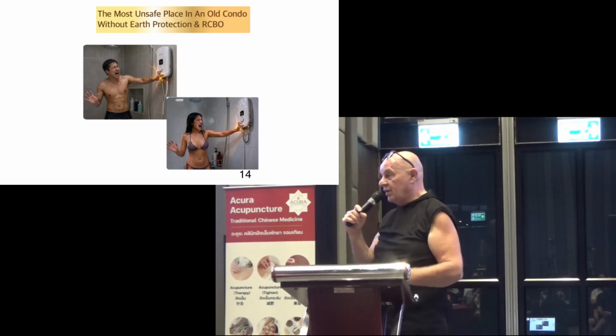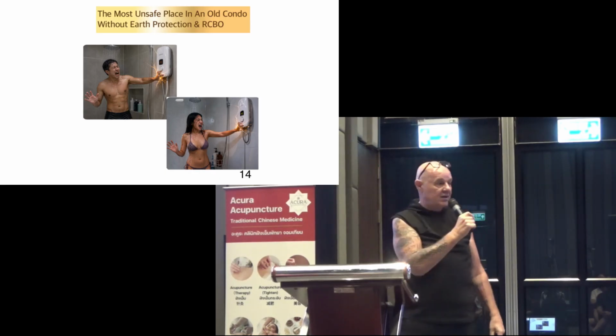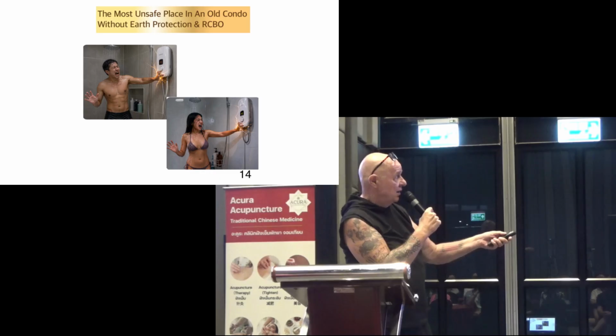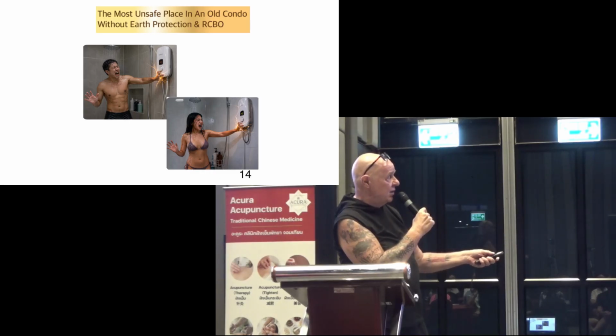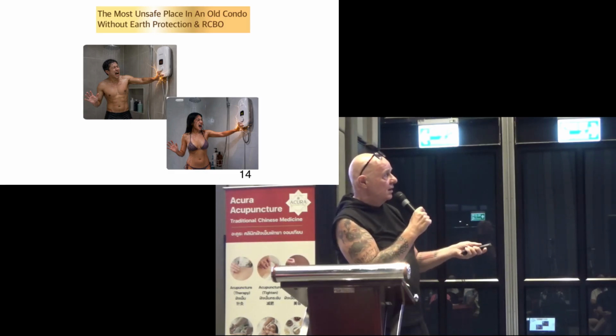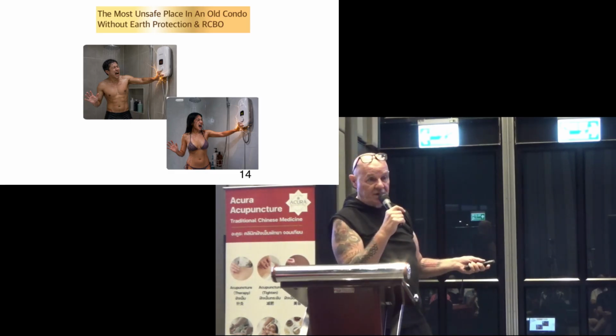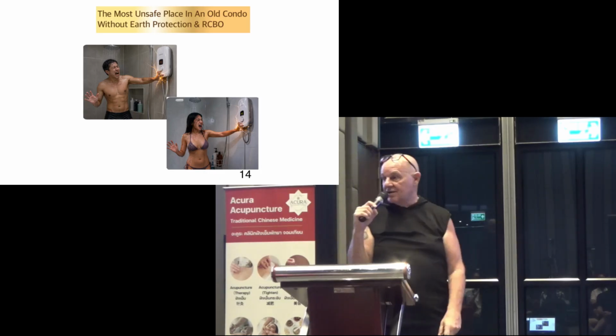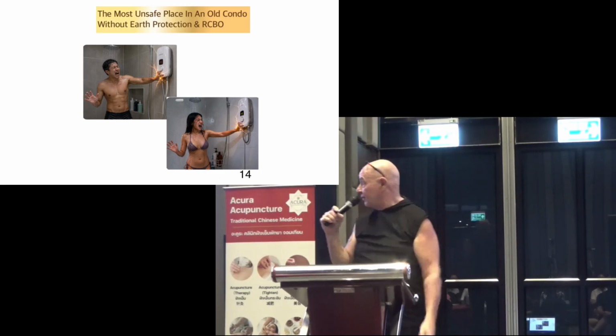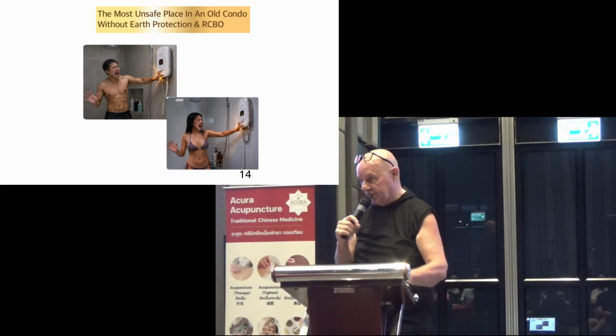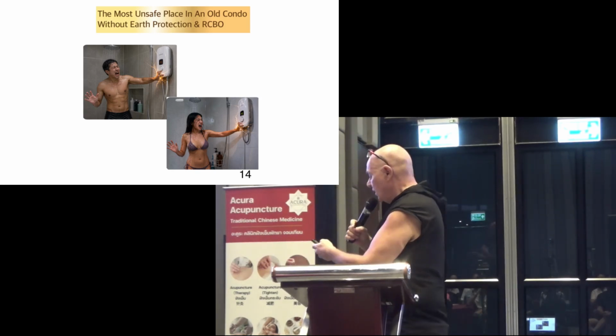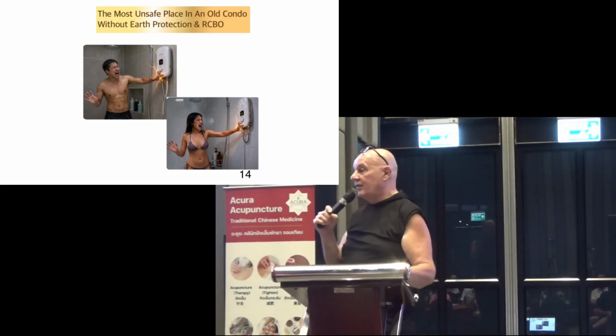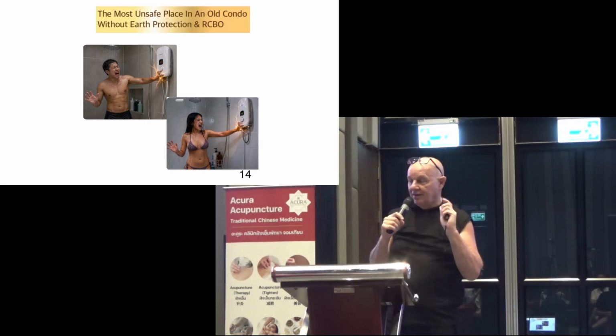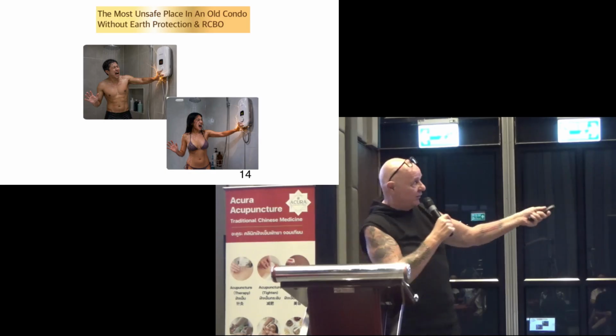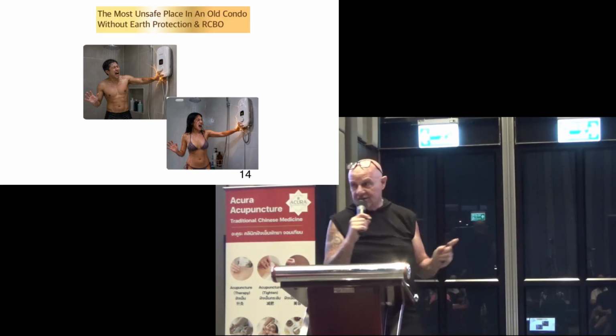Okay, this is your most unsafe place in a condo - if you have an electric heater in a shower and there's some sort of fault, there's water there, the amps is going to go through you to earth. And as I said, that's 18 point something amps. That's going to fry you. Now, if you don't have earth leakage in your condo and you have this setup, there is a solution.